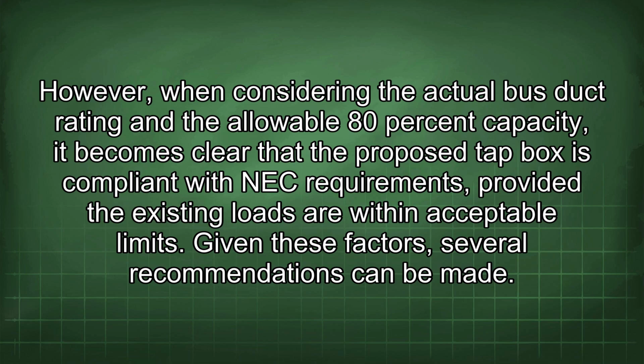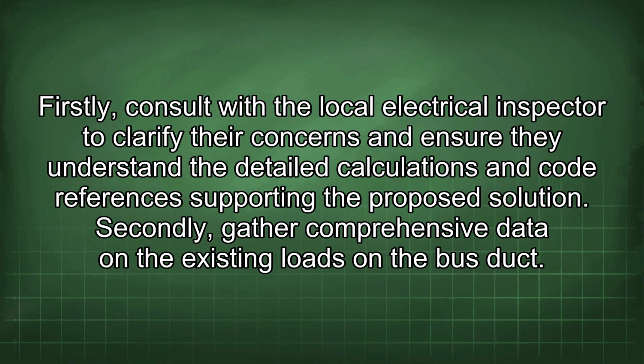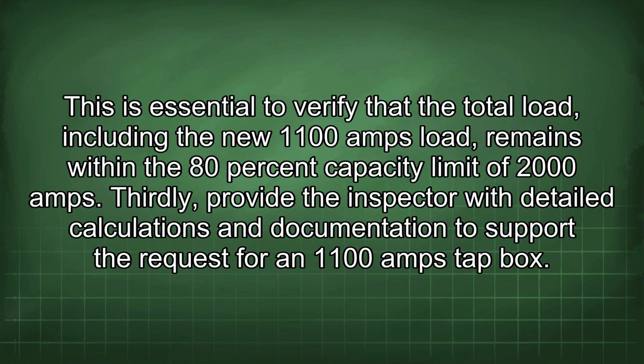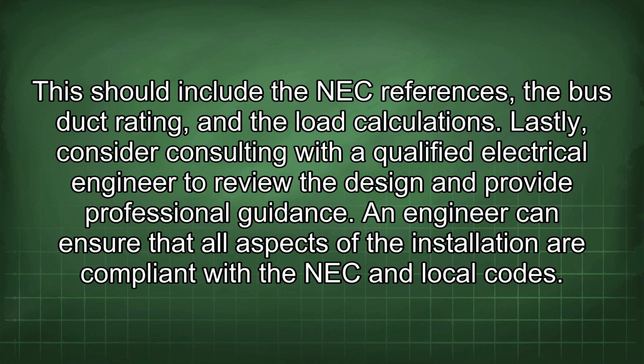Given these factors, several recommendations can be made. Firstly, consult with the local electrical inspector to clarify their concerns and ensure they understand the detailed calculations and code references supporting the proposed solution. Secondly, gather comprehensive data on the existing loads on the bus duct. This is essential to verify that the total load, including the new 1100 amps load, remains within the 80% capacity limit of 2000 amps. Thirdly, provide the inspector with detailed calculations and documentation to support the request for an 1100 amps tap box. This should include the NEC references, the bus duct rating, and the load calculations.